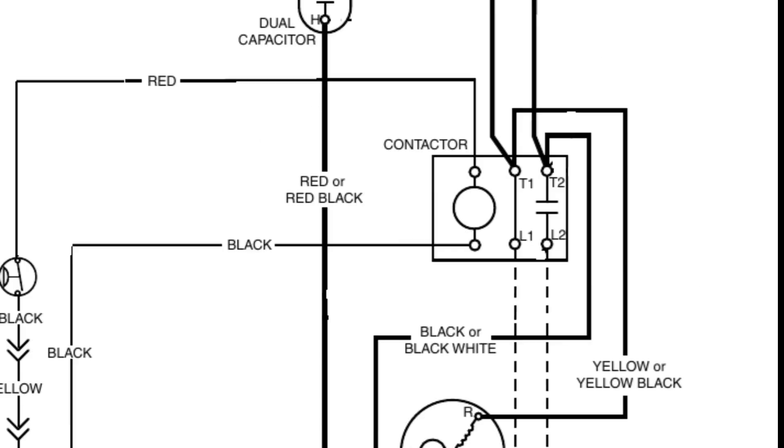And the reason why we call it control voltage is because we need some means to turn the high voltage circuits on and off so that we can control compressors and motors and pumps. So if we go back to our contactor as an example, we can see we have our high voltage flowing through there. We have an open switch or an open drawbridge, and we know this circuit has to be closed. That switch has to be closed in order for the circuit to be complete and the motors to actually run. And we do that with a low voltage signal. So when 24 volts hits that contactor, which comes ultimately from your thermostat, that 24 volts goes through a coil. The coil creates a magnetic field and that magnetic field pulls that switch closed on the high voltage line. And we now have a complete circuit on our high voltage and our motor can run.